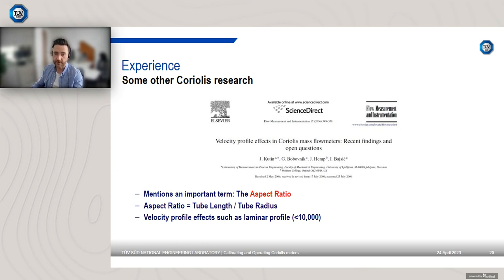So they found that velocity profile effects such as the laminar profile, and we're saying laminar starts around about the 10,000 and below Reynolds number. Some people quote 2,000. It depends on your entry conditions. So that was part of my doctorate research. You can actually have laminar flow persisting all the way up to 100,000 Reynolds number or so. It really depends when you have perturbations. So basically puffs and eddies creating swirls, which then creates a disturbance which moves towards less of a parabolic flow profile to more of a turbulent flow profile. We found that smaller aspect ratios have larger velocity profile effects.